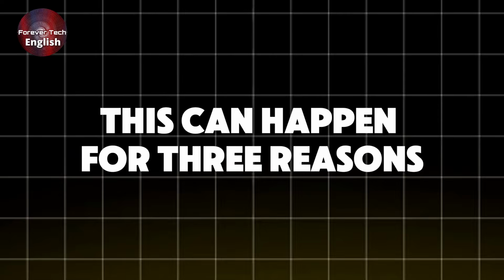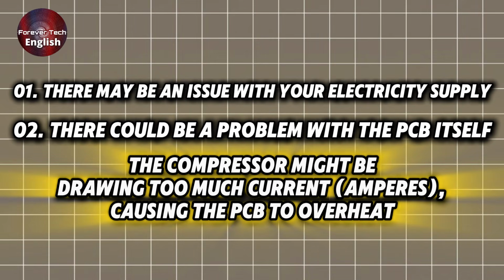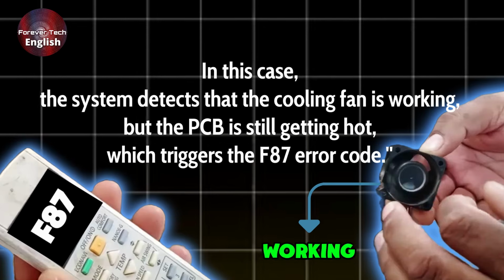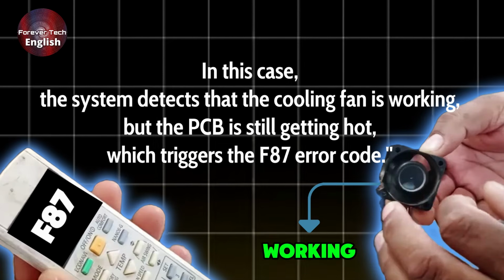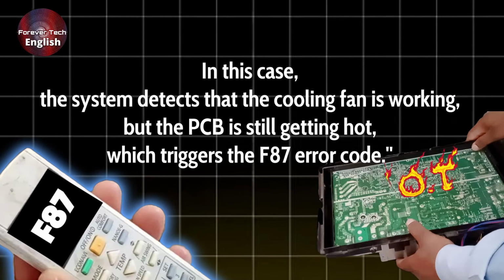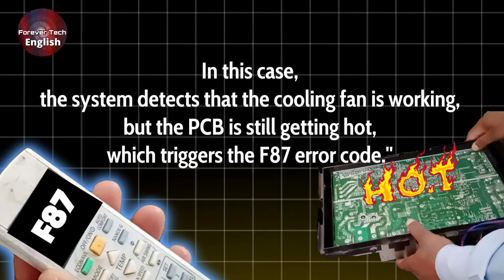This can happen for 3 reasons. There may be an issue with your electricity supply. There could be a problem with the PCB itself. The compressor might be drawing too much current, amperes, causing the PCB to overheat. In this case, the system detects that the cooling fan is working, but the PCB is still getting hot, which triggers the F87 error code.